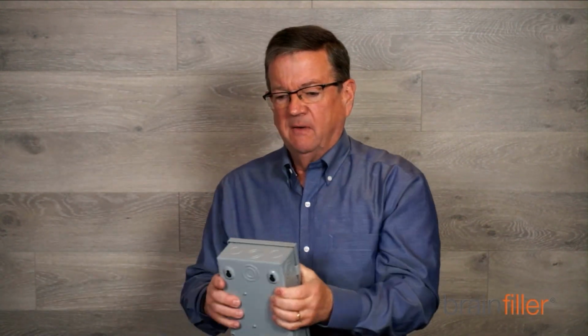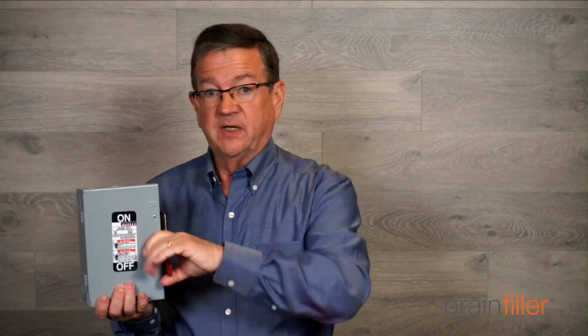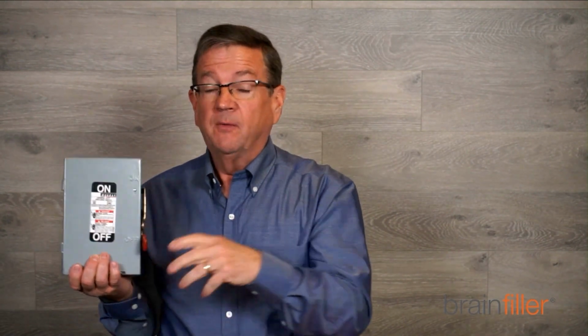But although I haven't heard of it happening, I can imagine it could, that if you're de-energizing, if this fails, maybe. But as I said, I really haven't heard it catastrophically failing. Now, there are failures, and I've investigated cases where someone has de-energized, they switch this off. Fortunately, they measure absence of voltage and find out this thing is still energized because the jaws in here failed. But I could picture, be a stretch, but a potential catastrophic failure, although I've never seen one in that case.